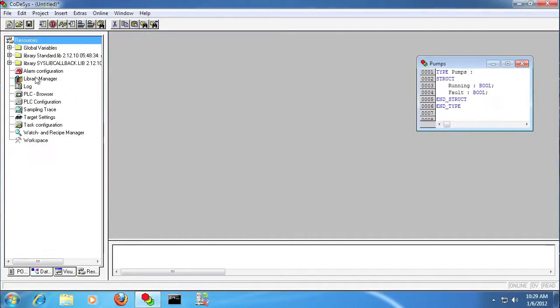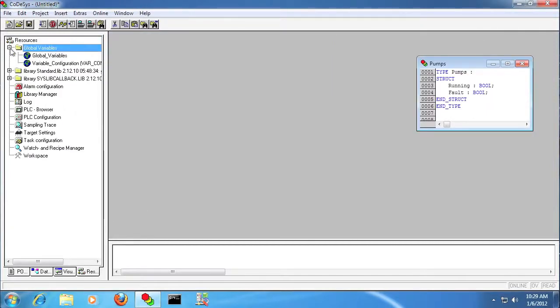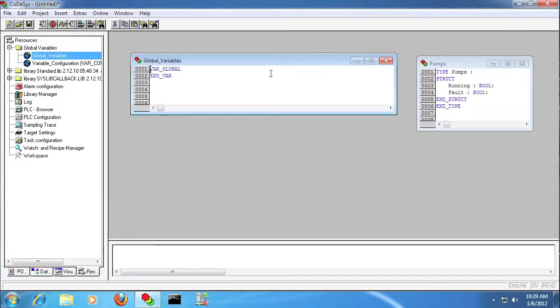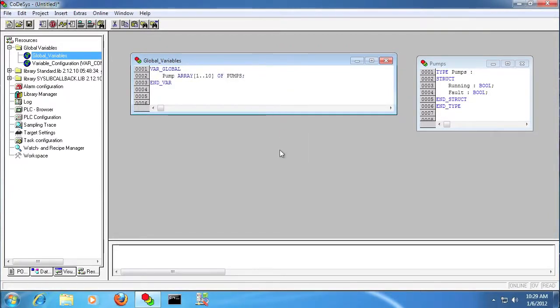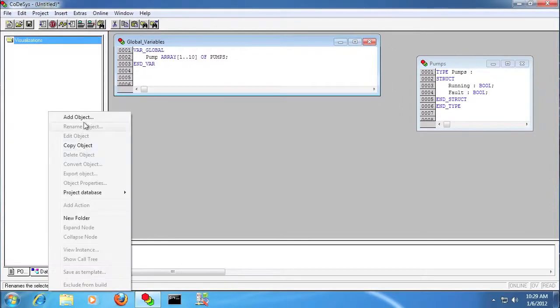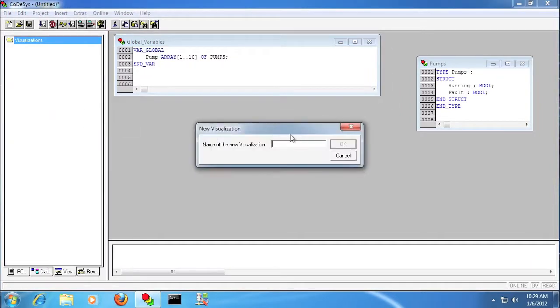And I'm going to create a global variable, it's actually going to be an array, called pump with 10 elements of that same custom data type, pumps. So each one of those pumps has a running and a fault bit.